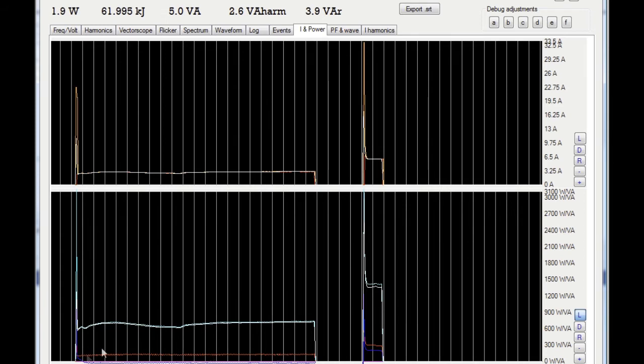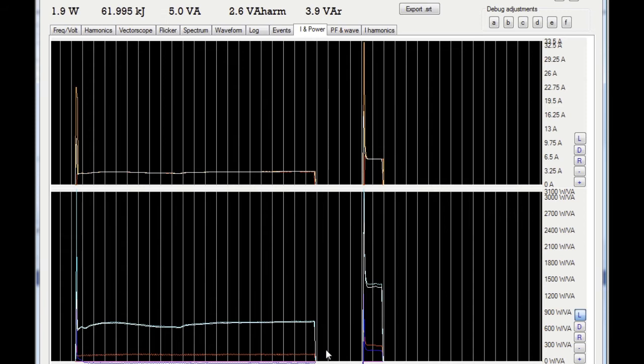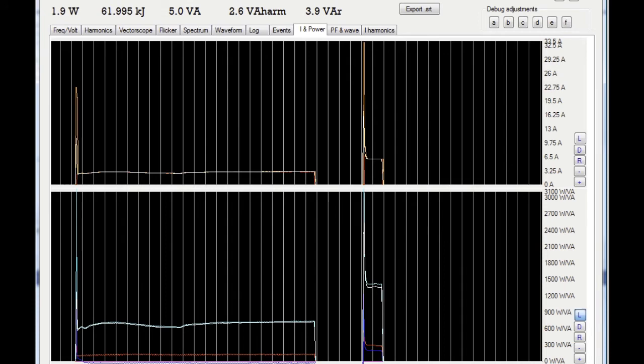And red here is distortion power. When a current waveform is different in shape to the voltage waveform, not all of that current does useful work. Some of it just gets wasted effectively. This is a measure of how distorted the current waveform is and how efficiently the current is being converted into energy, or rather, how efficiently energy is being transported on that current. So let's actually take a look at the waveforms now.